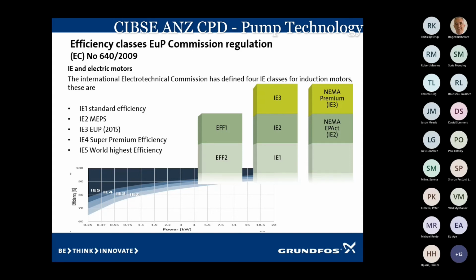And you can see by the graph down the bottom, it's not so much up on the peak where we've got a big change, because they're all very similar at that point, but it's when we're actually pulling to the left is where we're starting to see a bigger gap between the efficiencies, and this is where we're running our pumps and motors a lot at those points.